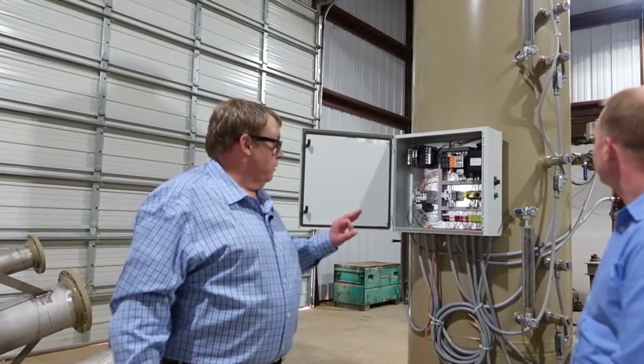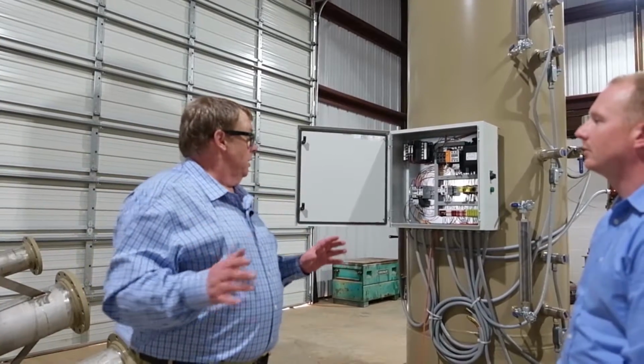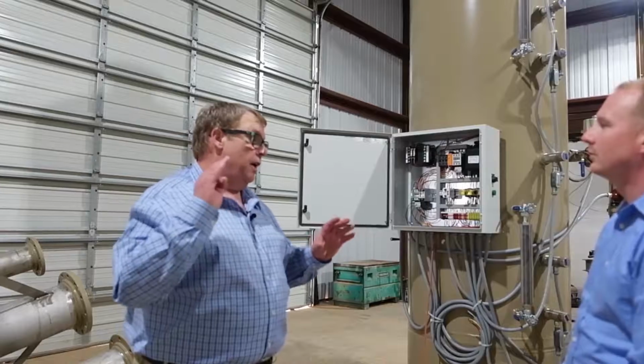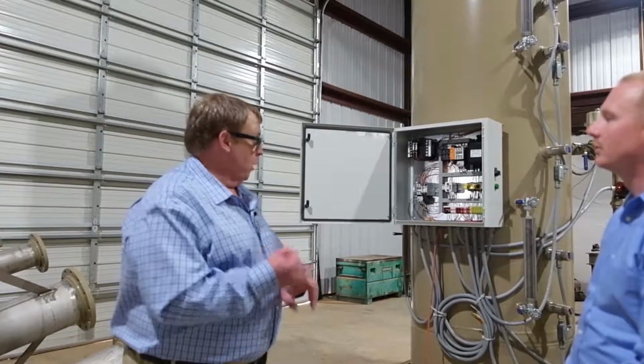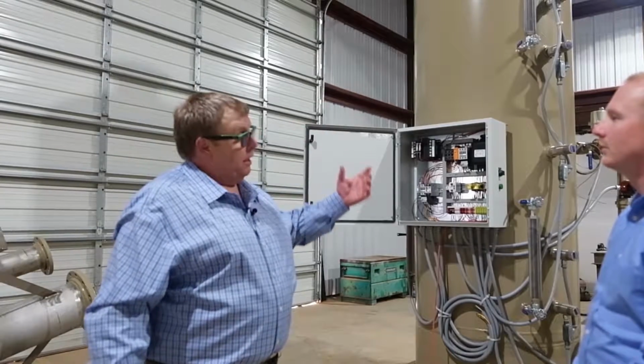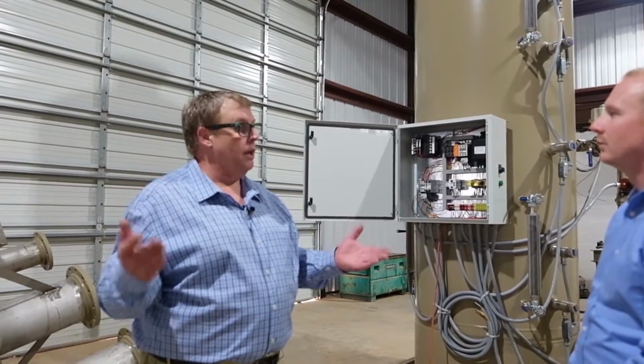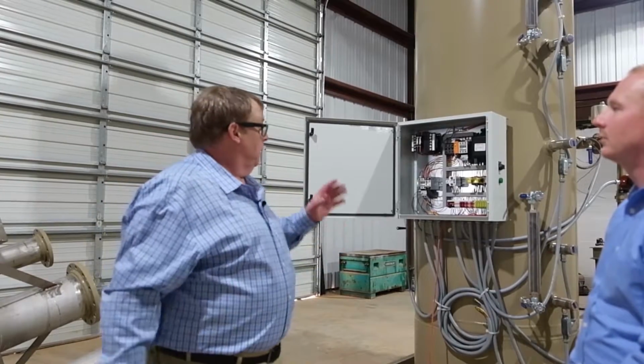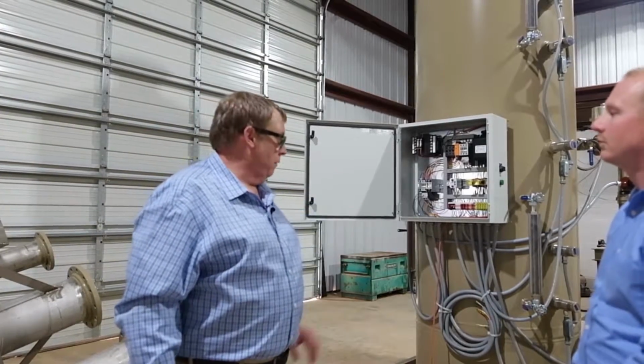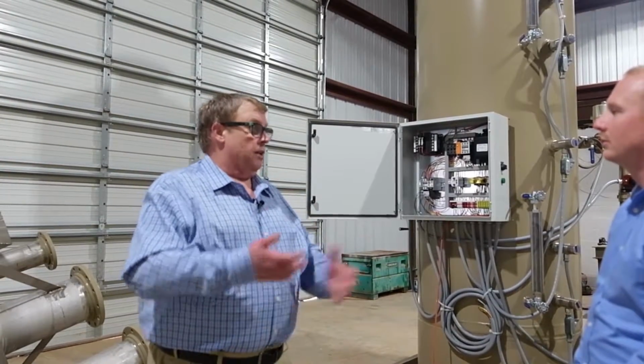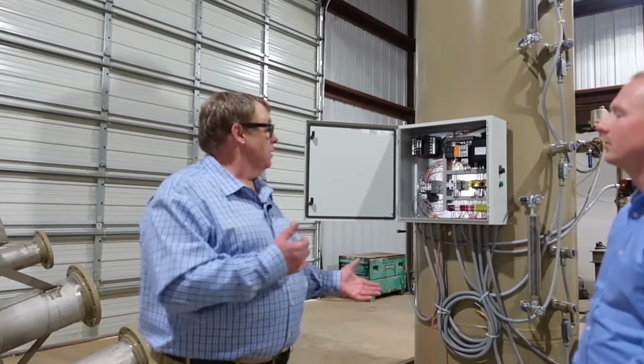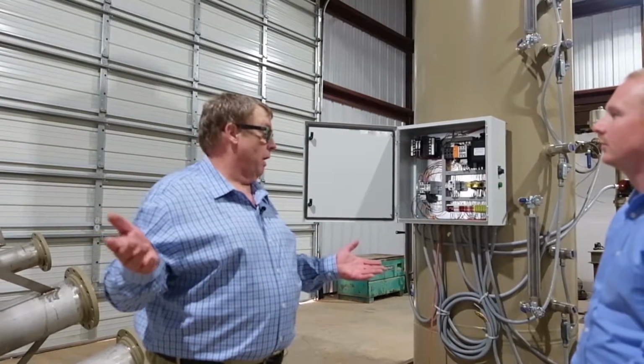One last thing I want to point out is Vaprox has a service team that's out in the Permian Basin, and these guys are constantly, day in and day out, doing service calls and regular scheduled PMs. Those regular scheduled PMs, they'll wash flame arresters and make sure we keep the crud out. They bring down the pilot system, make sure that the venturis are cleaned out and that we've got a good solid pilot. Just do a once over across the entire flare. They'll also perform a Method 22 test, which will let the client know that they are remaining in compliance. And all of this is done on just a regular scheduled maintenance call.